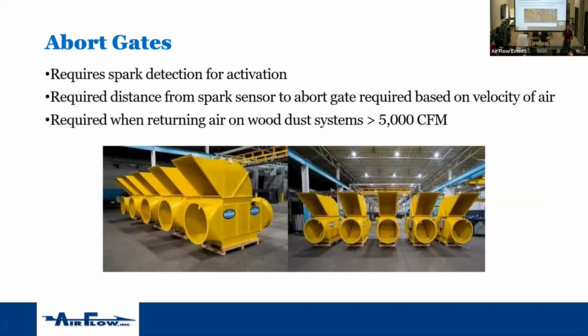If you're dealing with wood dust, again, NFPA standards are all going to change and get combined into one. Currently, if you have a wood dust facility, it's mandatory that if you're above 5,000 CFM and you're returning the air to the space, you need to use an abort gate. And that's because you can have a fire without having an explosion. So you've got to have a way to get that smoke outside of the space rather than back into the building.